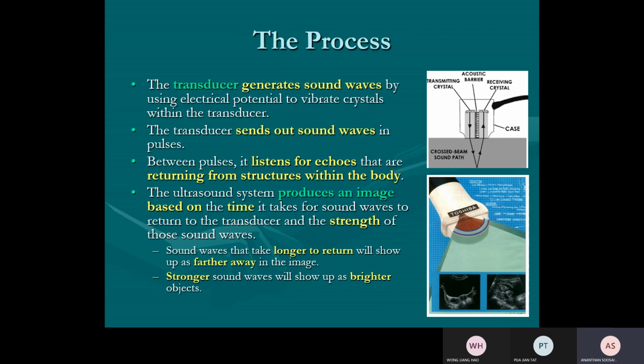Our focus is on the transducer: how ultrasound is produced, what is inside, and how it receives the signal back. The transducer generates sound waves, ultrasound, by using an electric potential to vibrate a crystal. There is a crystal in between, like a parallel plate. We use an alternating electric field, and the frequency of the electric field is close to the frequency of the ultrasound. Vibrating the crystal produces the sound. So why does the crystal vibrate? That is what we are going to explore. A brief idea: the transducer generates sound by oscillating a crystal inside using an electric potential difference.